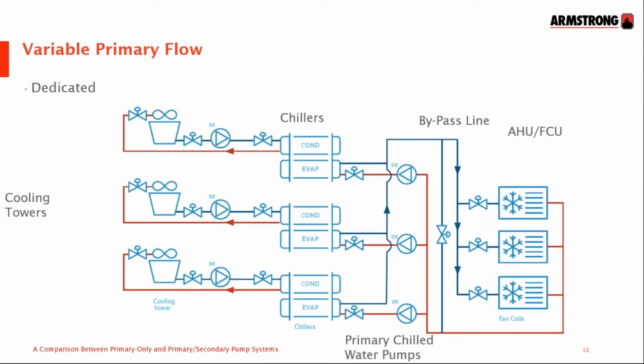Now in this case, as before, we have a choice between a dedicated system where pumps are dedicated for each chiller. We will be looking at headered shortly, but what you'll notice first is that there's just 1 set of pumps circulating water through the chillers and all the way around the building to the air handling units or fan coils or chill beams before it comes back again. The pumps, as with the secondary chilled water pumps previously, are controlled to maintain a constant differential pressure at the remote load, either by using the traditional method of having transducers connected to the BMS, wired all the way back to the mechanical room at great cost, or by using sensorless control.